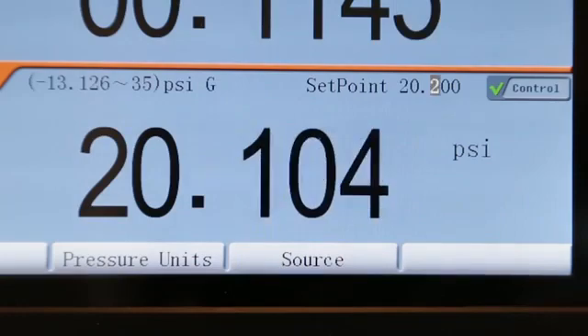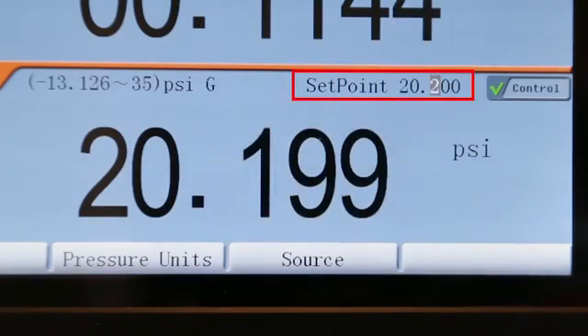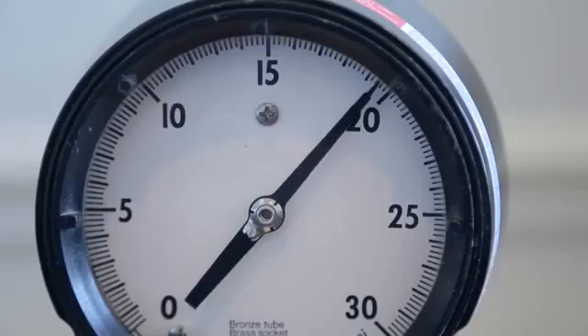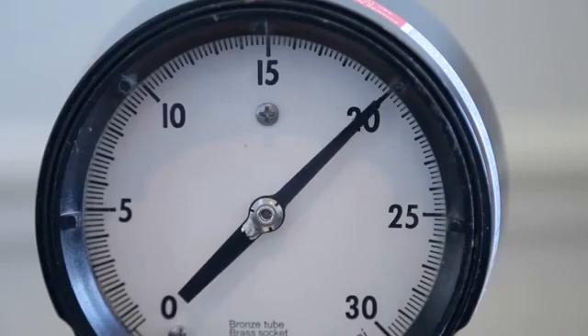For calibration of analog dial pressure gauges, Additel has included a jog pressure feature that allows you to make small changes to the controlled pressure manually so the needle can be set right on an increment. Simply use the right or left arrow keys to raise or lower the pressure to the desired level.